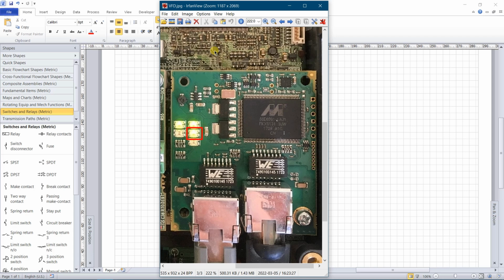If the LED is red and lights constantly, then the board is in exception state. One flash shows a configuration error, where the expected identification differs from the real identification. Two red flashes mean that the IP address is not set, and three red flashes mean that the name of the station is not set. The third LED is the error LED.